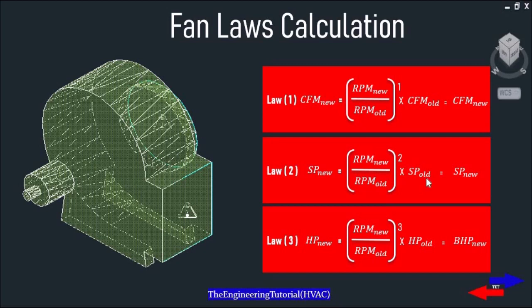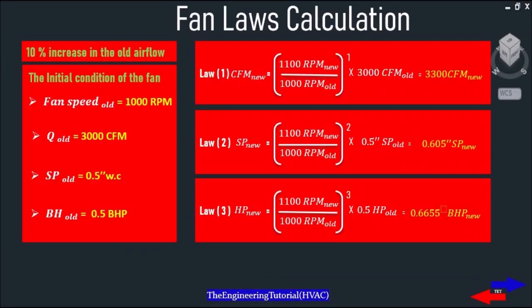The third fan law tells us that the horsepower increases as the airflow changes, and it is calculated according to the cube of the speed ratio. Fan Law 3: Horsepower new equals (RPM new divided by RPM old) cubed, multiplied by Horsepower old, which gives us brake Horsepower new.